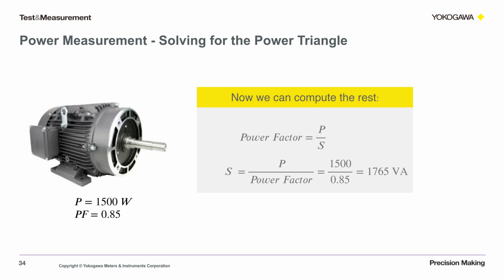Using our equation for power factor equals P over S, we can solve for S, which equals 1765 volt-amps. If we want to solve for phi, or reactive power, we could do that as well. If I was installing this motor, I could use this data to verify that I'm using the correct winding type, gauge, and right motor drive, which will provide power to that 3-phase PWM motor for the given load.